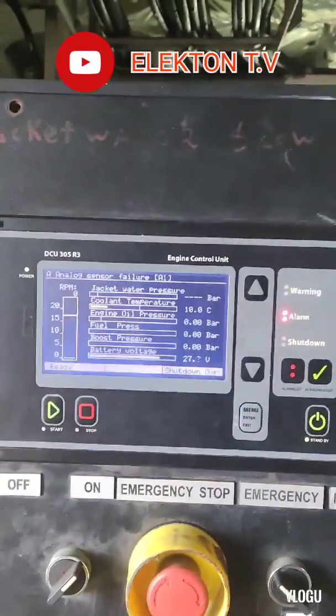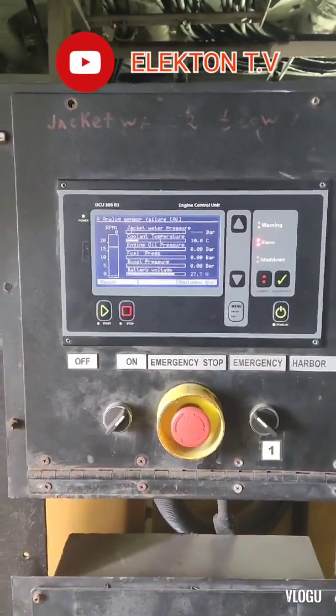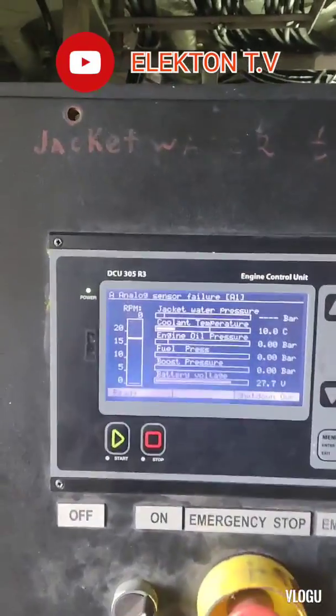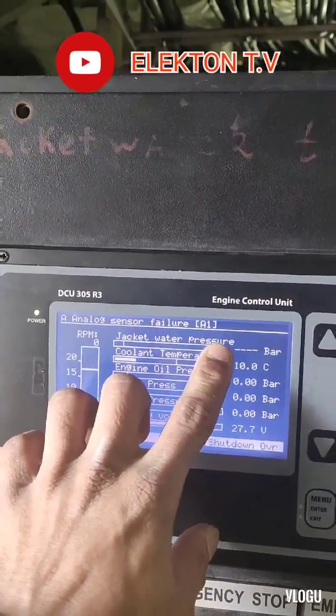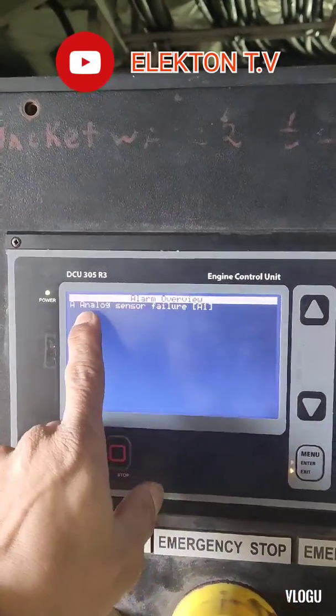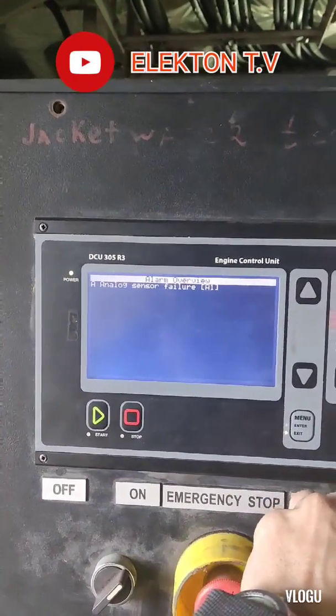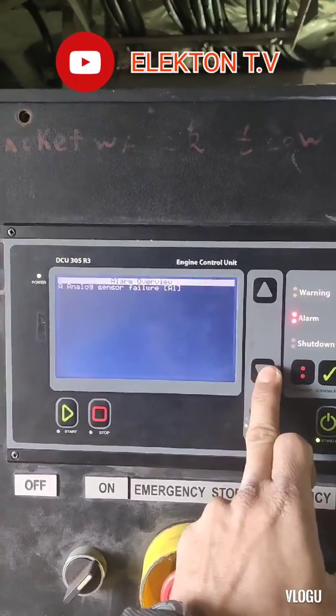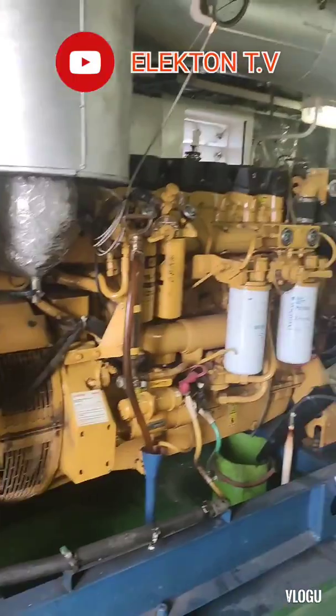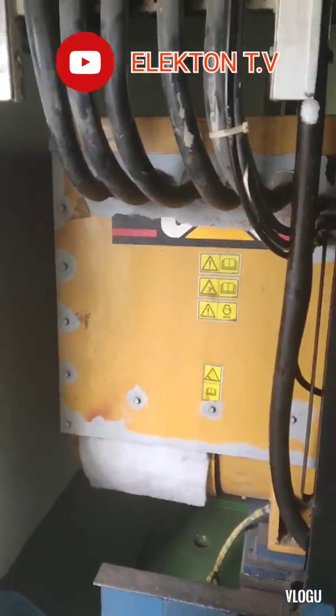Hello guys, welcome back to my YouTube channel Elekton TV. For today's video, it's about a Caterpillar generator. The problem is the alarm showing 'analog sensor failure A1'. Based on the engine control unit, the analog sensor failure A1 did not indicate exactly where the alarm is or what kind of alarm we need to check. All of our generators on board have the same alarm.